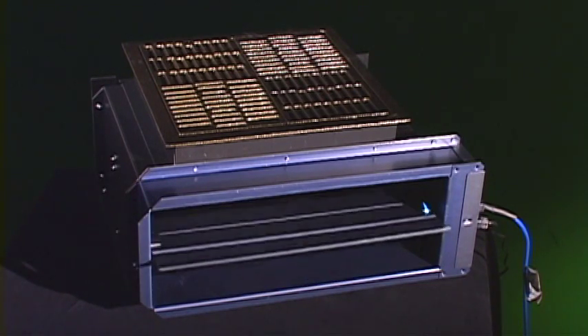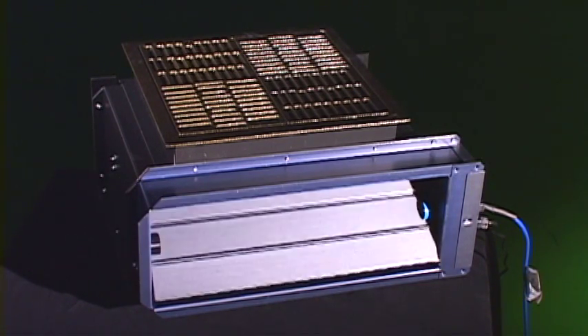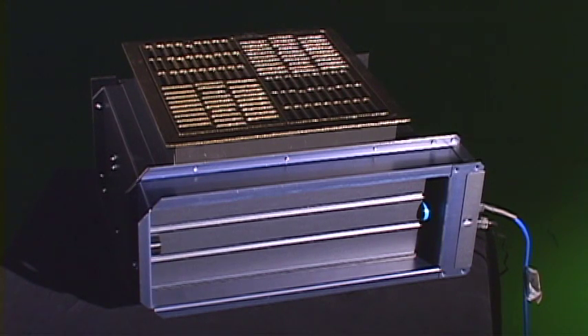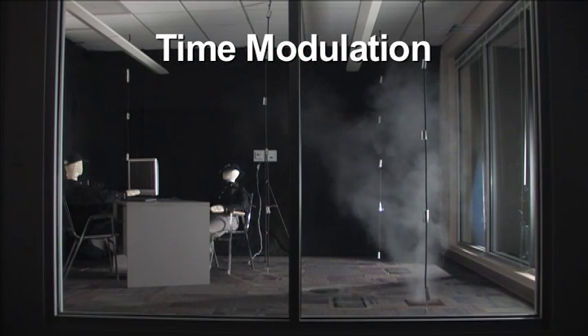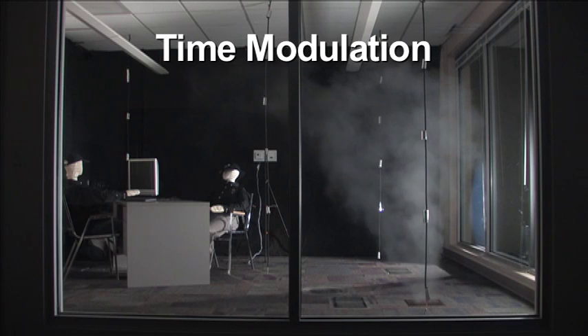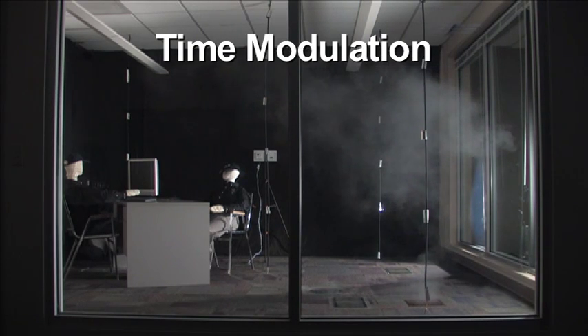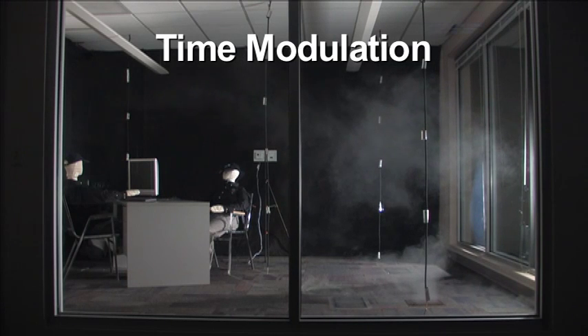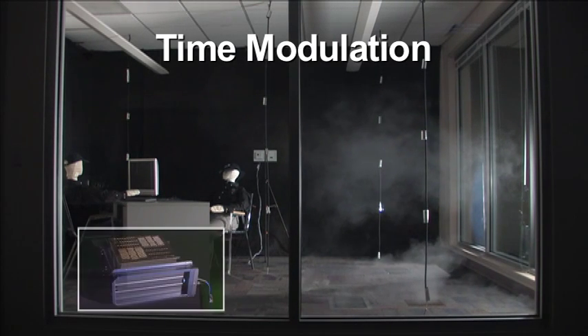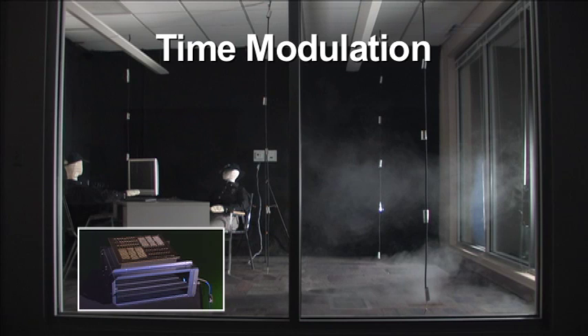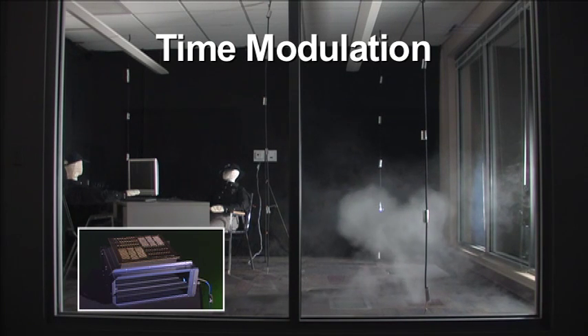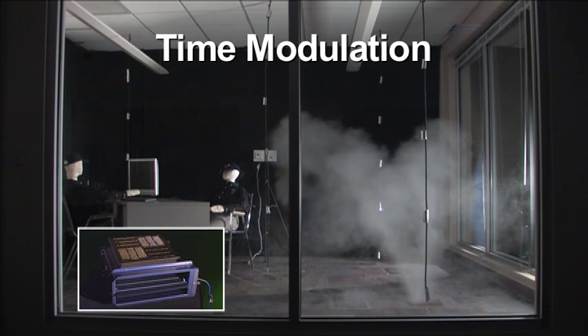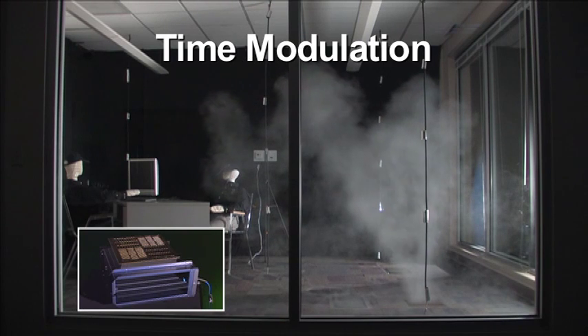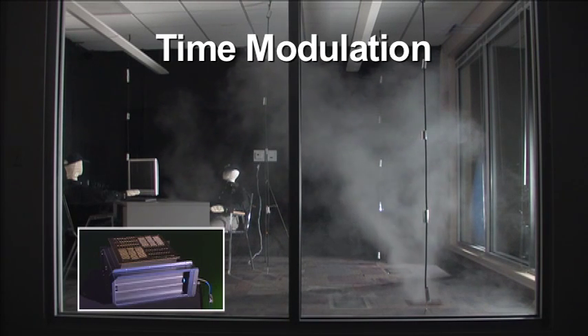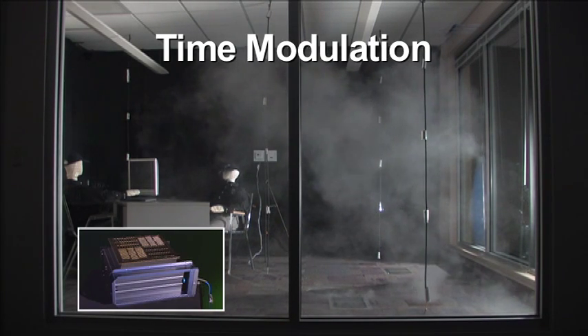These open-closed cycles vary in length to exactly match load conditions. As you can see, the cycles are kept short so that occupants have a sensation of continuous air movement. The diffusers take turns opening so plenum pressures can be maintained. The diffuser you now see is also operating at about 25% airflow and is virtually the same as the first example, except this one has a time modulation air valve.